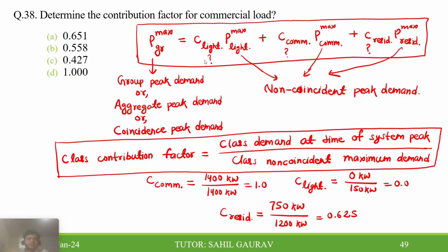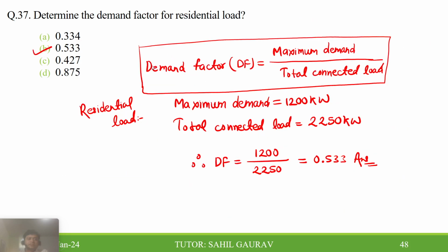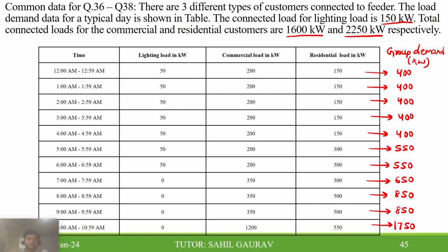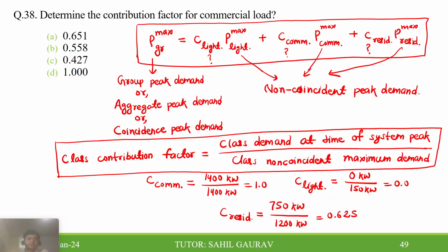Here we can see that this P_GR max is known, P light max is known, P commercial max is known, and P residential max is known, but the contribution factors for lighting load, commercial load, and residential load are all three unknowns. Then you cannot find it with this expression from the table. Then what is the other way? The other way is that you have to remember this other expression.